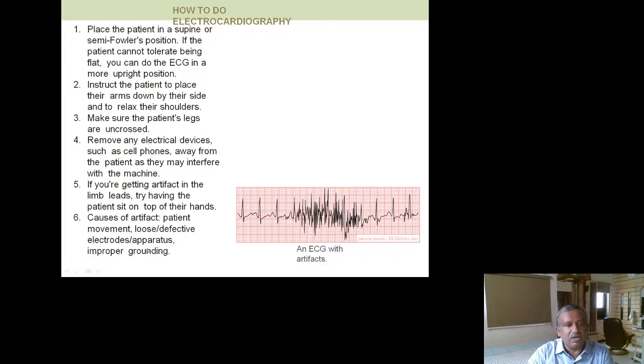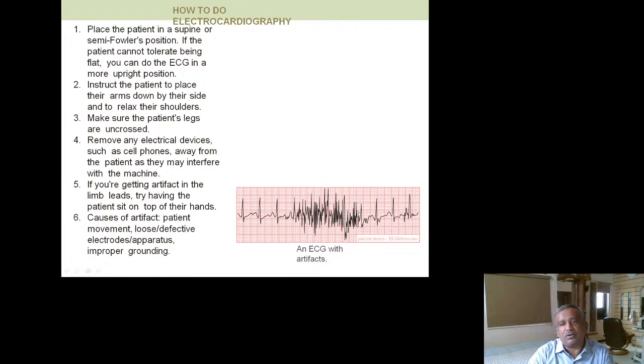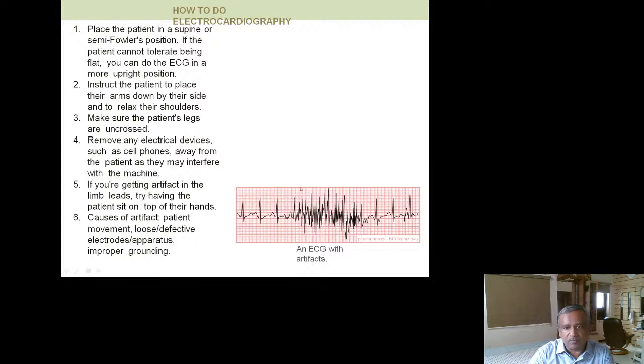Artifacts can be caused by patient movement, loose electrodes, improper apparatus, or improper grounding. If you are taking the ECG with the machine on electrical mains rather than battery supply, improper grounding can cause this type of artifact. It is therefore important to ensure proper grounding of the electrical supply.